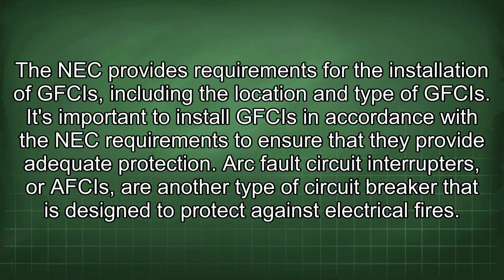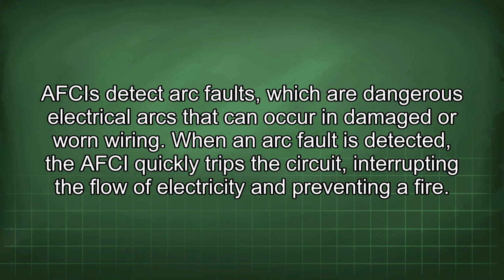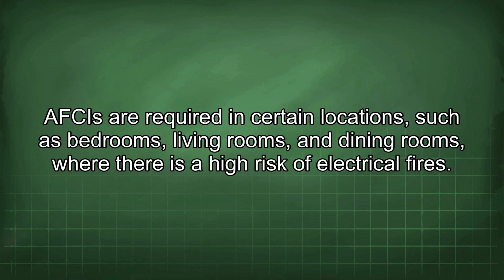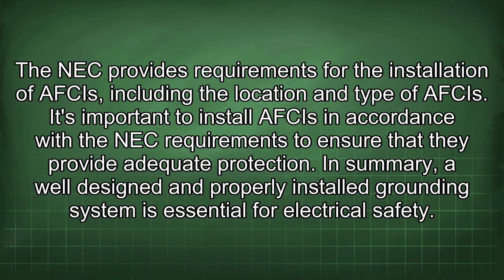Arc fault circuit interrupters, AFCIs, are another type of circuit breaker that is designed to protect against electrical fires. AFCIs detect arc faults, which are dangerous electrical arcs that can occur in damaged or worn wiring. When an arc fault is detected, the AFCI quickly trips the circuit, interrupting the flow of electricity and preventing a fire. AFCIs are required in certain locations, such as bedrooms, living rooms, and dining rooms, where there is a high risk of electrical fires. The NEC provides requirements for the installation of AFCIs, including the location and type of AFCIs. It's important to install AFCIs in accordance with the NEC requirements to ensure that they provide adequate protection.